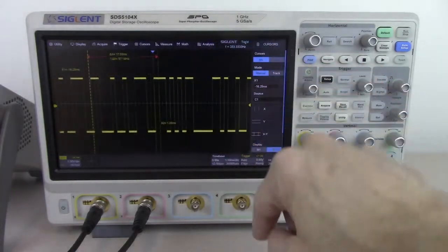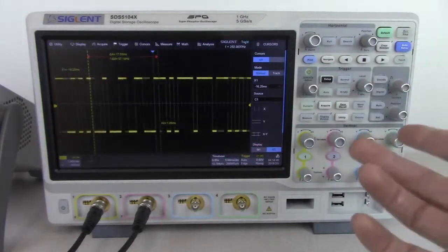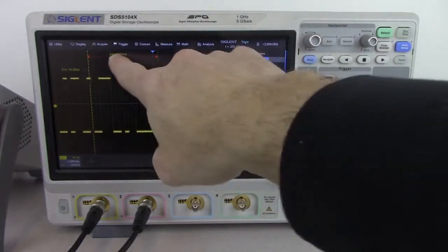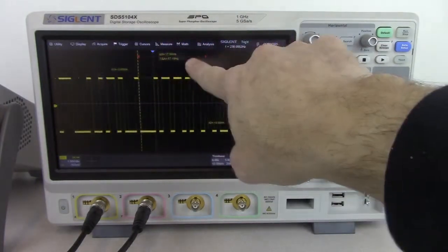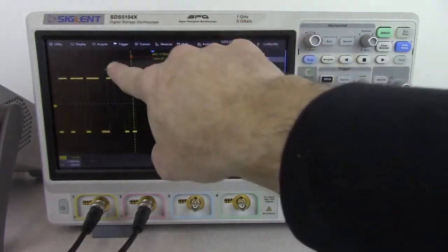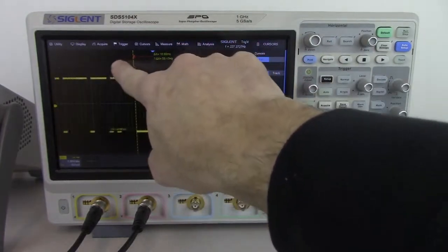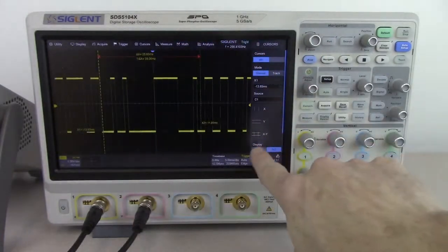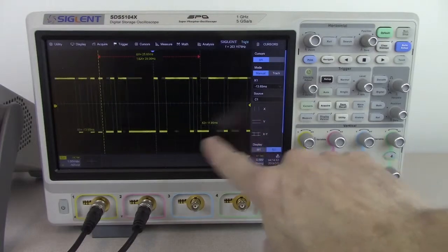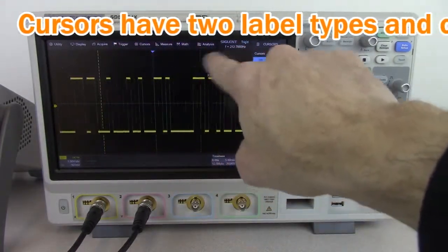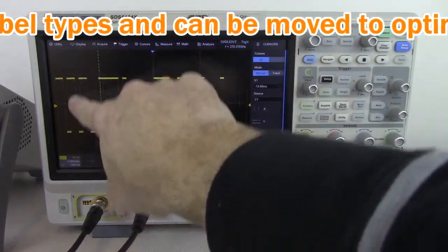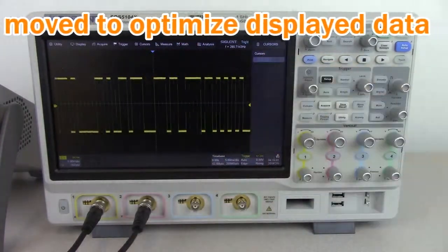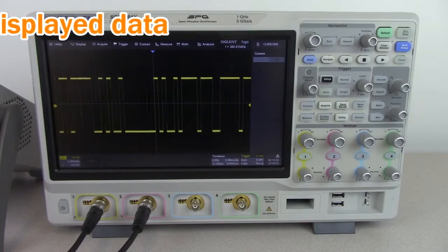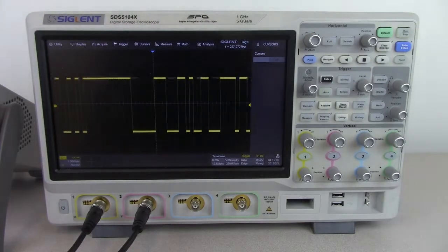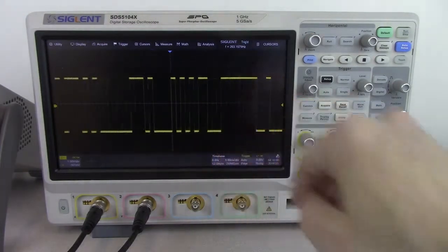We're just going to turn on the X and Y. And again, we're just trying to make things easier for your on-screen viewing. To move the cursors, you can simply drag them back and forth. We can also move labels for each individual cursor. We can lengthen and contract. We can also change the display type. This is M2. We can change it to M1. And now we have a concise version, and we can move that anywhere on screen. So that can also be very useful if you're looking to take different pictures or key in on specific areas on the display.